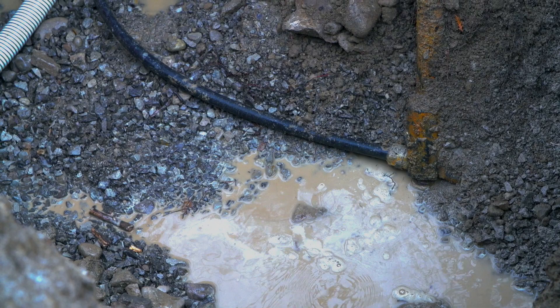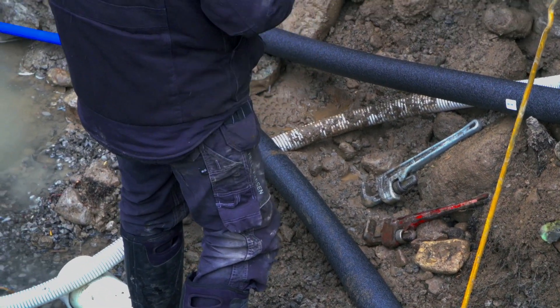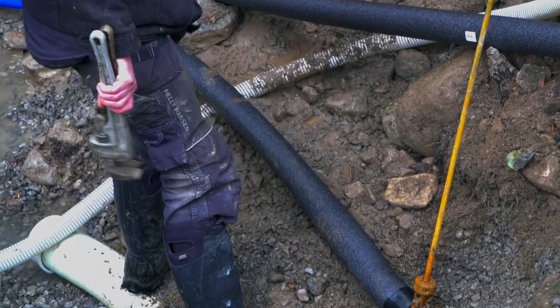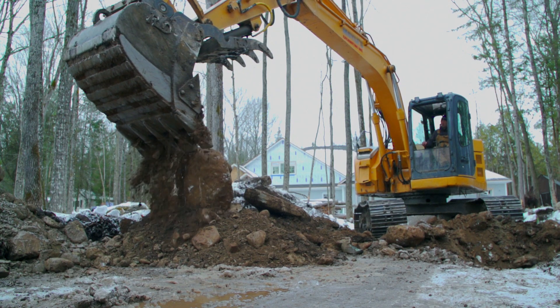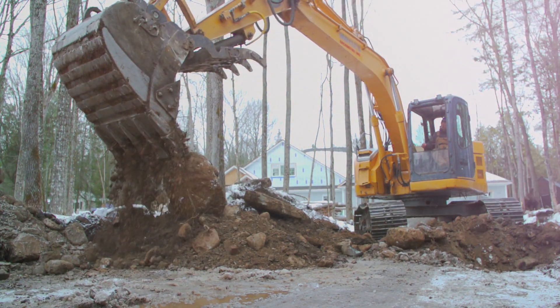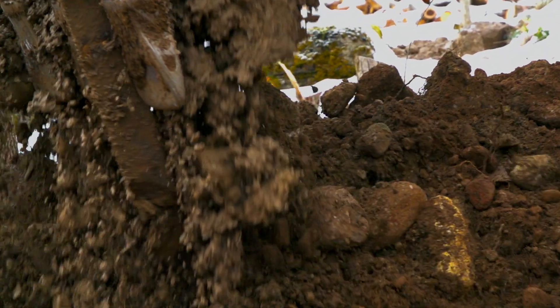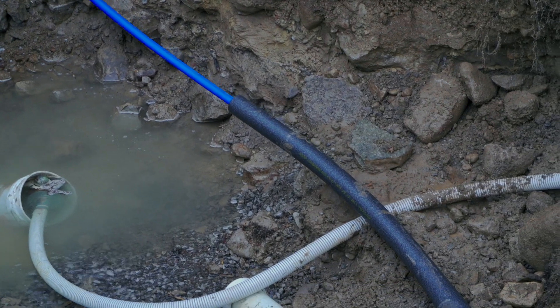While the trench is currently full of stone, rock aggregate, and sharp material, this excavation will be replaced with sand. A lot of times they'll put styrofoam board or a urethane-type foam insulation over top of the pipe, as well as the foam sleeves that are being applied now. The important thing is that we don't want to backfill with rocks and rubble, because something could shift and move in the future. With nice clean sand, things will be safe for years and years.